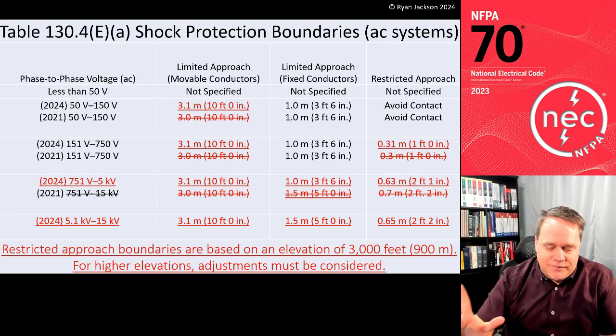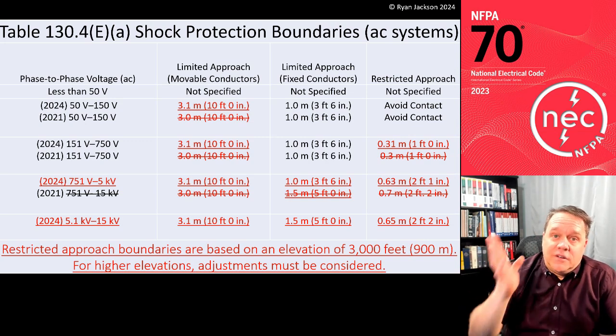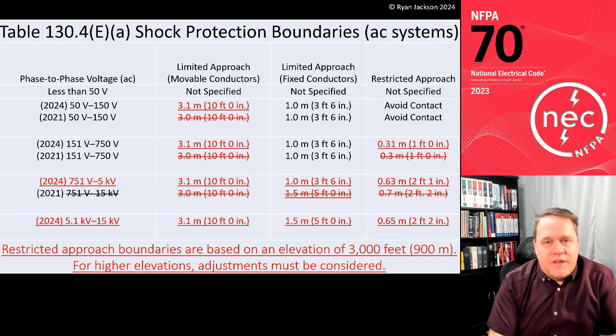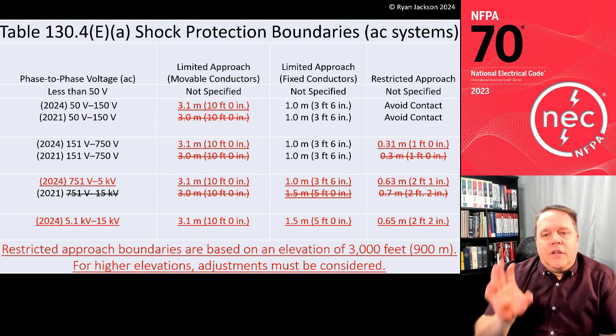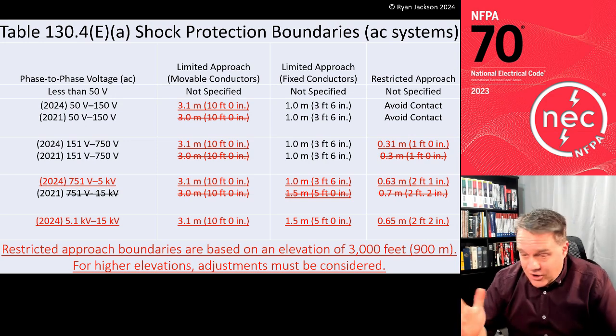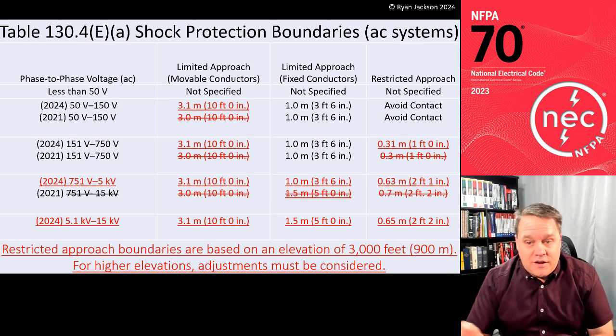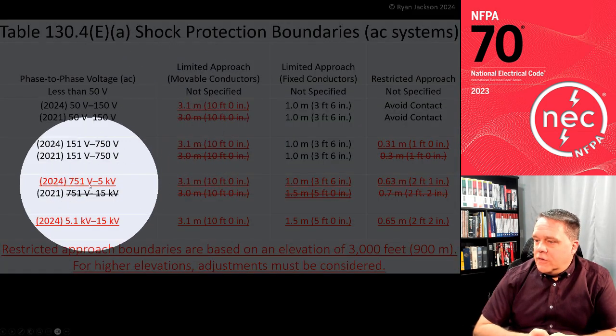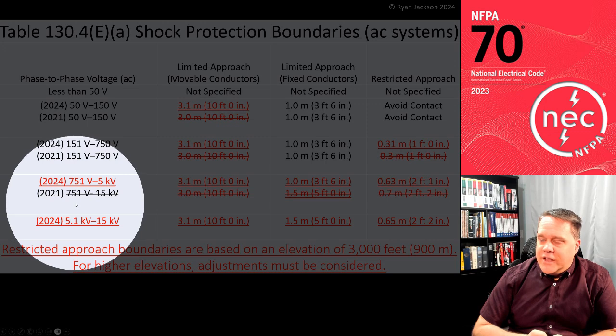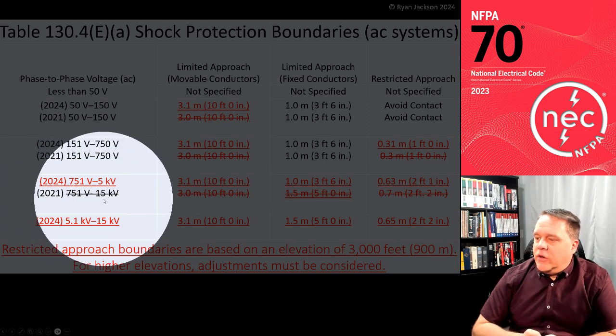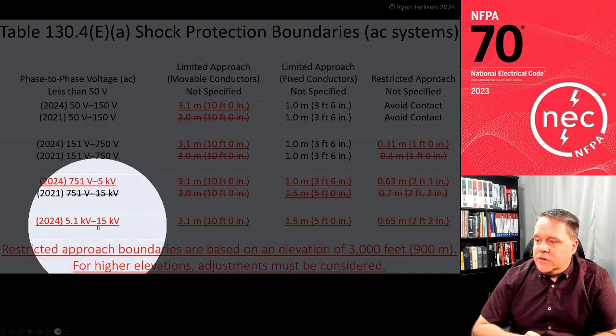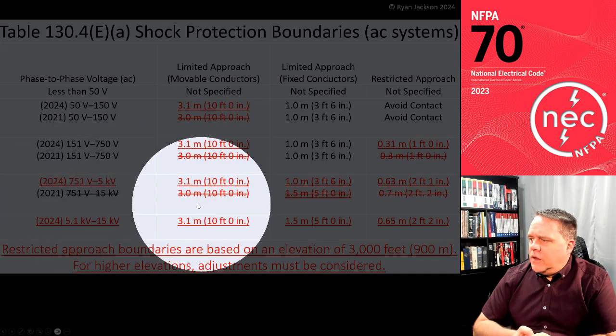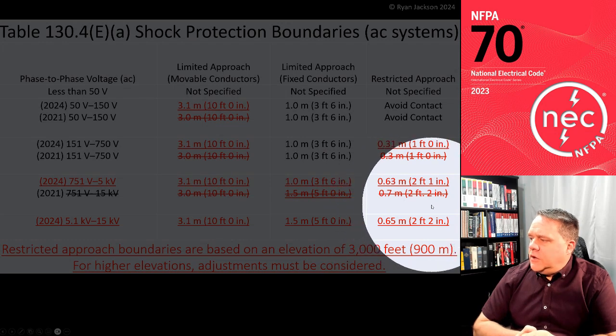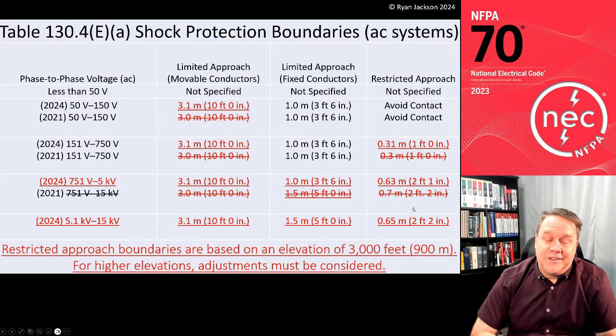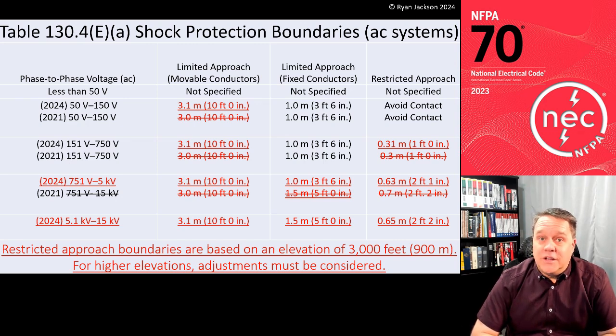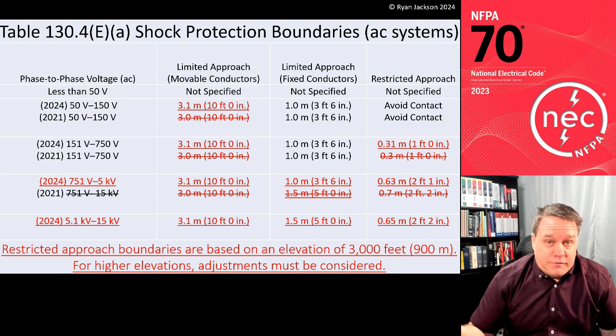I know it, but it is what it is, okay? The fact is, previous versions of this table did not satisfy OSHA. All right, so the shock protection boundaries changed, and often it changed by 1 inch, right? I mean, seriously, look over here. In the 2021 code, it's standard, we had 751 through 15,000 volts, and now we changed it 5,000, 15,000. But look over here all the way to the right, where it used to be 2'2". Now it's 2'1", and it's like, oh, seriously? You changed it for 1 inch. It didn't comply with OSHA before, okay?